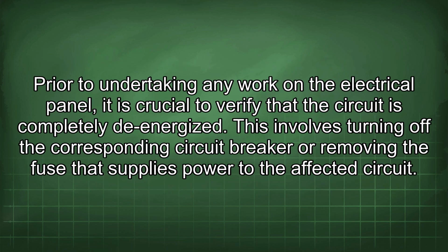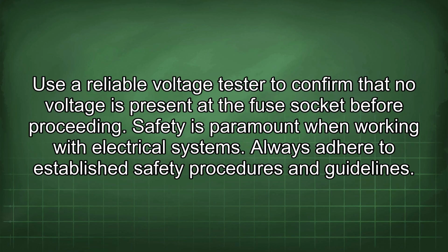Prior to undertaking any work on the electrical panel, it is crucial to verify that the circuit is completely de-energized. This involves turning off the corresponding circuit breaker or removing the fuse that supplies power to the affected circuit. Use a reliable voltage tester to confirm that no voltage is present at the fuse socket before proceeding.